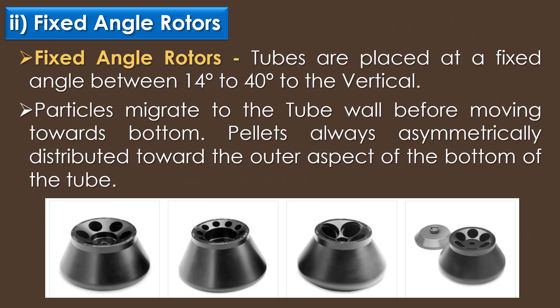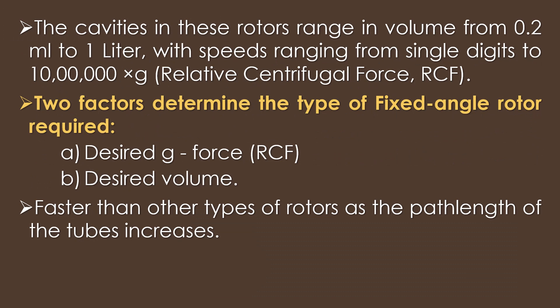The second type of rotor is fixed angle rotors. Fifth set angle rotors are the most ubiquitous rotors used in centrifugation. In fixed angle rotors, the tubes are placed at a fixed angle between 14 degrees to 40 degrees to the vertical. In this rotor, particles migrate to the tube wall before moving towards the bottom. Pellets are always asymmetrically distributed towards the outer aspect of the bottom of the tube. The cavities in these rotors range in volume from 0.2 ml to 1 litre, with speeds ranging from single digits to 10 lakh relative centrifugal force.